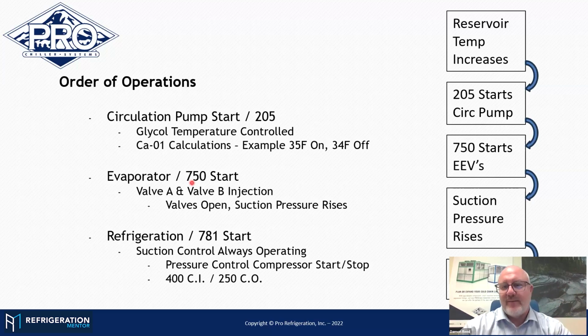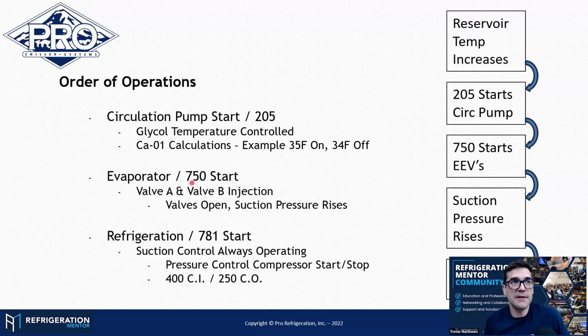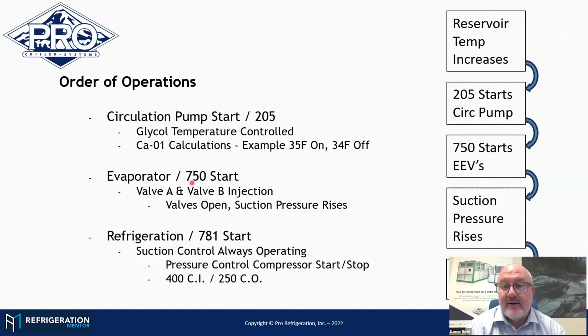But I always start with this order of operations. This is constant, and I always come back to it, because before I jump off into the more complicated diagnostics, it's really important to focus on this simple order of operations. What I like about that, and we talk about this all the time, is that as technicians in the field, we'll go in thinking it has to be some big, advanced problem. But 90+% of the time it's a basic issue. You've got a dirty condenser, a sensor that failed, a transducer that failed. Well, it could be a leak, but that's not usually an advanced troubleshooting problem.